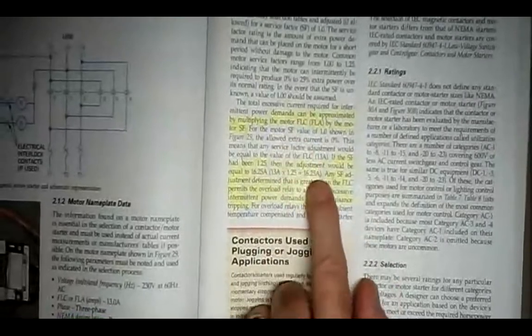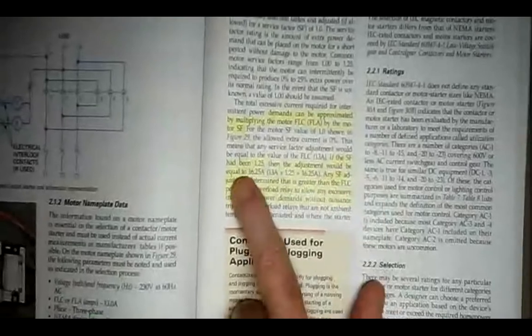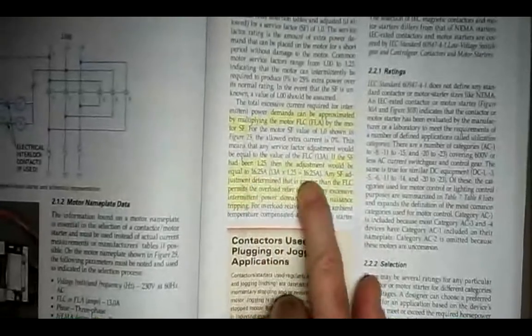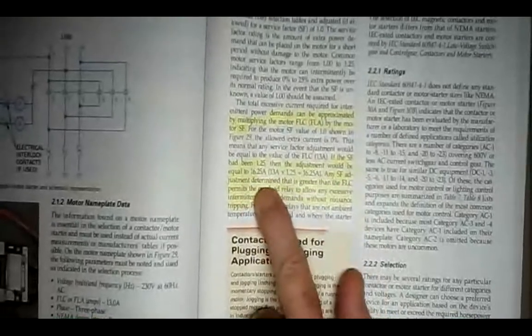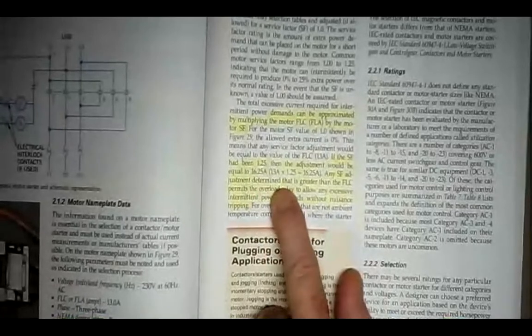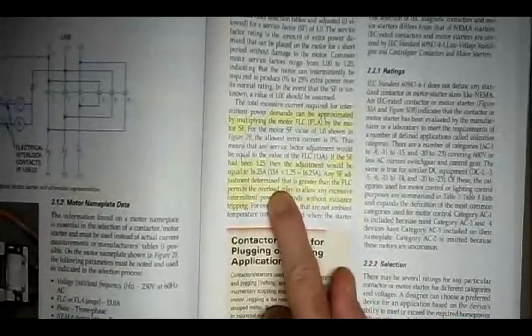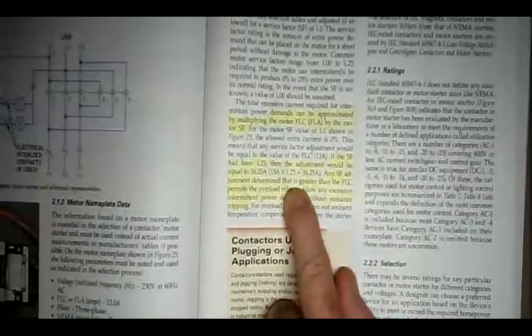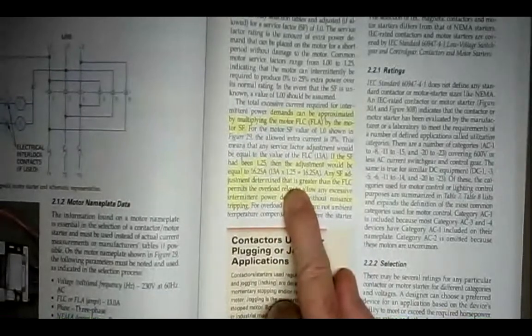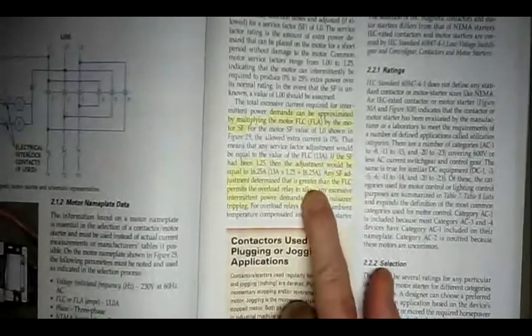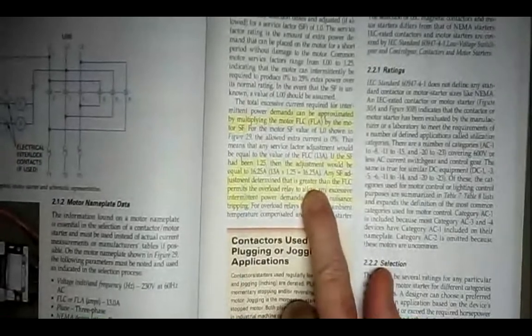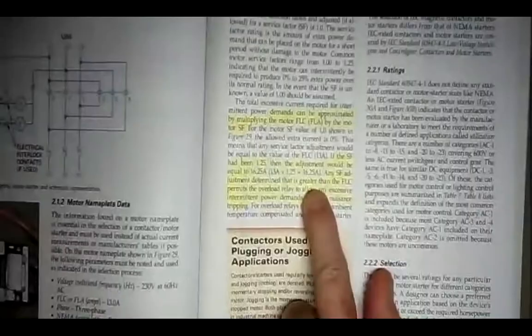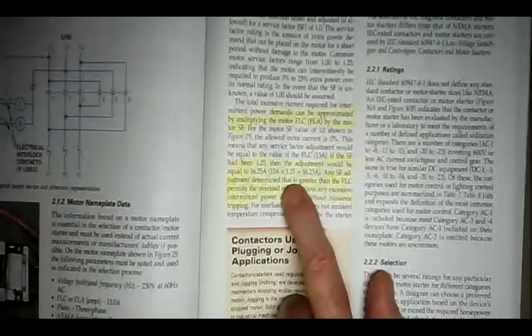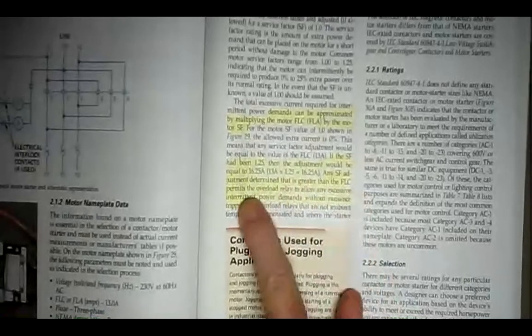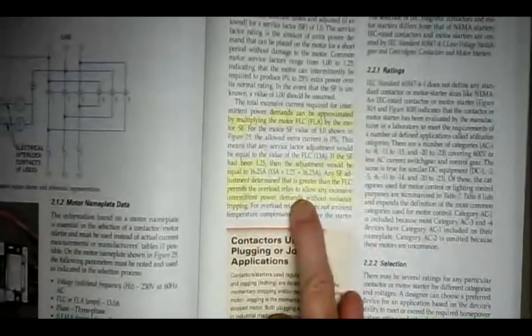For short periods of time, you don't want to do that forever, but it says if the service factor had been 1.25, then the adjustment would be equal to 16.25 amps. It's 13 amps is what they were saying was the running current at full load, and they're multiplying it times the service factor, 1.25. And they're saying you can actually put 16.25 amps on that motor without hurting it as a service factor. Most service factors are 1.15. Some motors are 1.25.